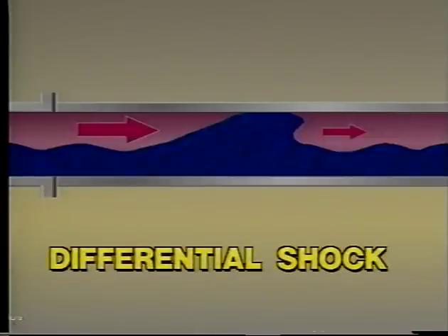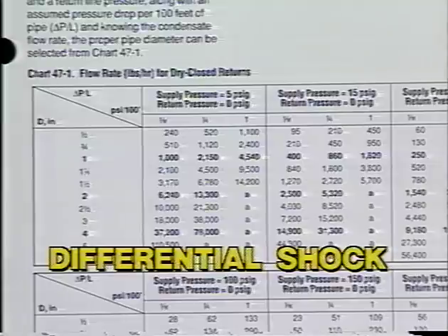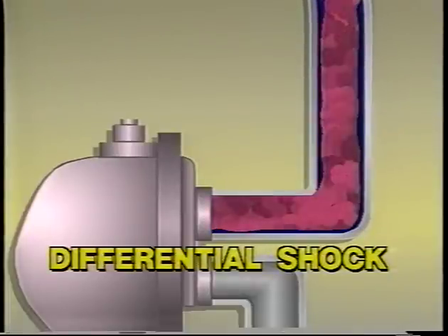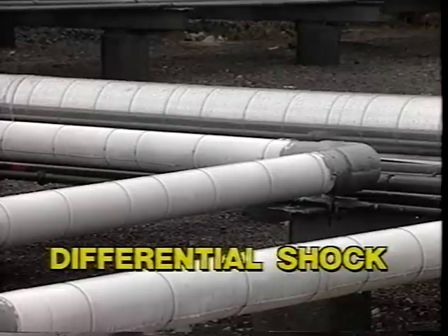Prevent differential shock in biphase systems by providing return lines that are properly pitched and of adequate size. Avoid draining equipment with long lines to the trap and insulate condensate lines whenever necessary.